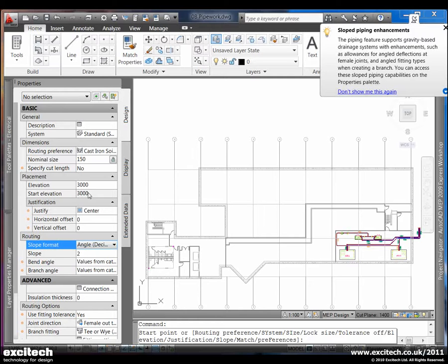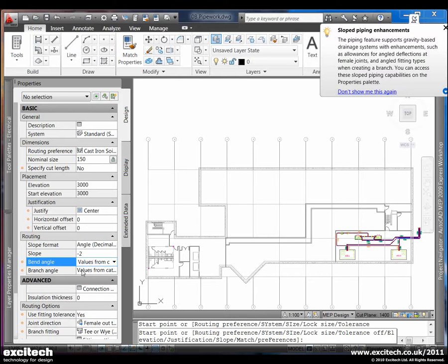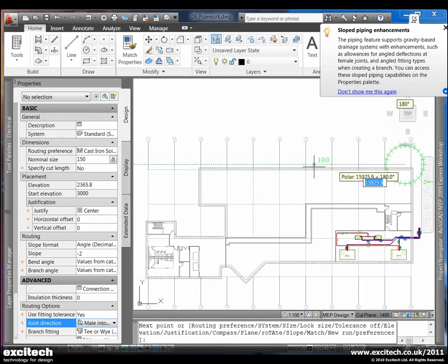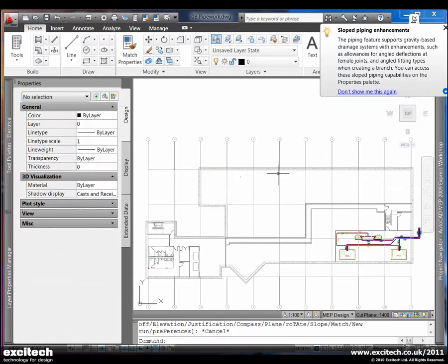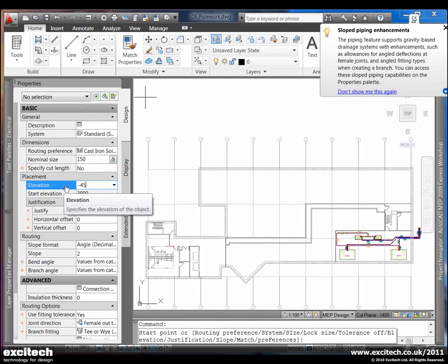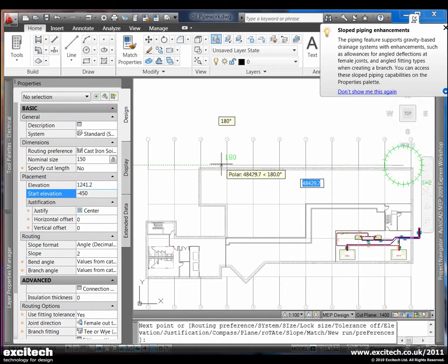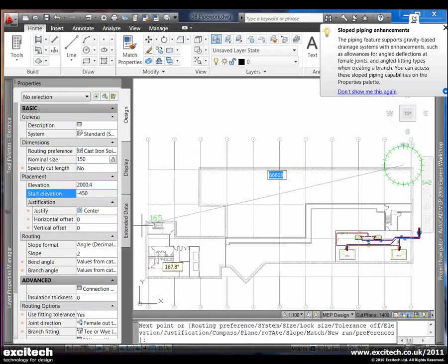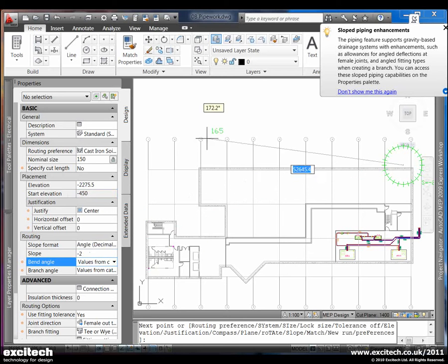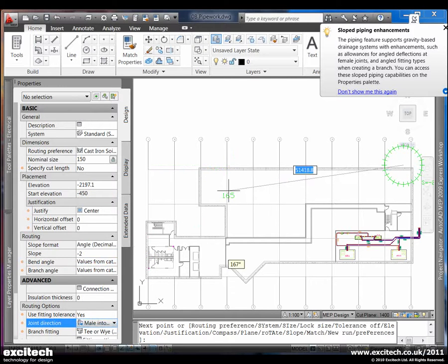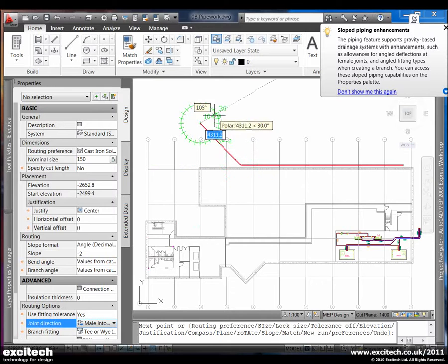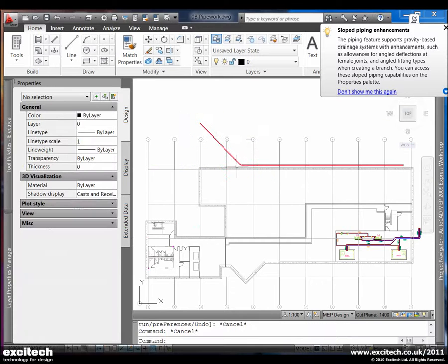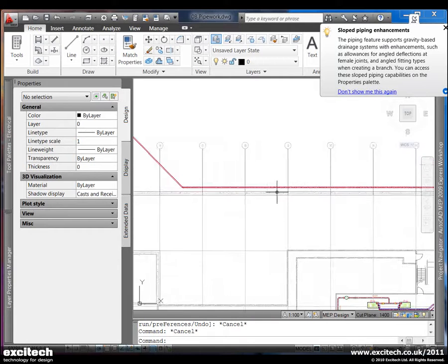If we go to the pipe tool, we notice that we can set a slope for this. In this case, we want it to slope downwards in the direction that we are selecting, so we'll set that to minus two and male into female. I'm just going to run this pipe along the side of the building. In this case, we'll choose an elevation of minus 450, which is at the level of the foundation, and just take that in the minus two direction, male into female. And you'll notice that it goes male into female.